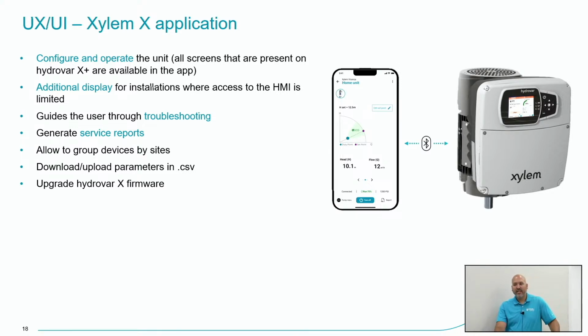And a question we typically get is, a lot of this equipment is installed in places without cell service. The idea is here you would download the Hydrovar X firmware on the mobile application or obtain it while you have cell service. Then you can go down into said mechanical room or basement, wherever it may be, that has limited cell service, and still download that firmware via the Bluetooth connection. So you won't necessarily have to worry or be concerned about having proper cell signal.